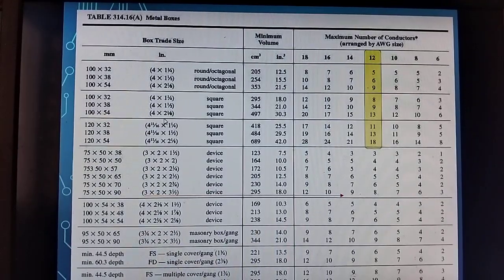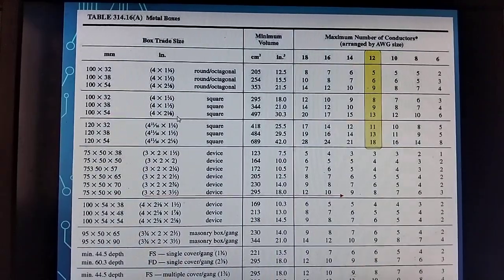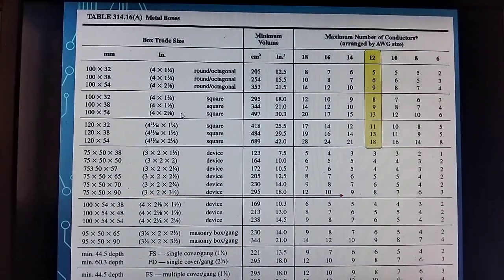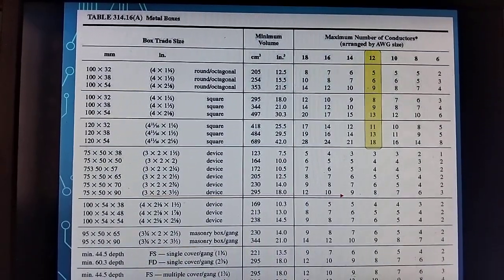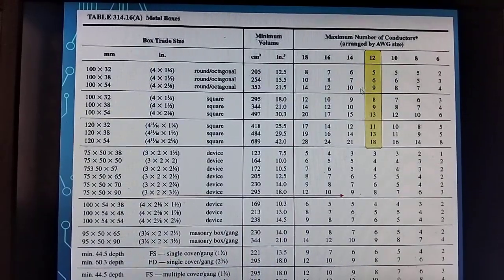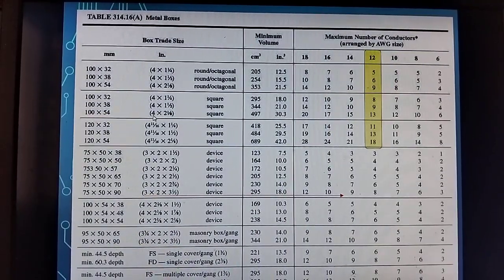Let's say even size 2 and 1/8, size 13. Instead of a round or octagonal box that only allows 9, you installed 12 individual conductors, so it's not allowed to use this octagonal. You must use a square box. Let's say a 4x2 and 1/8 square box.